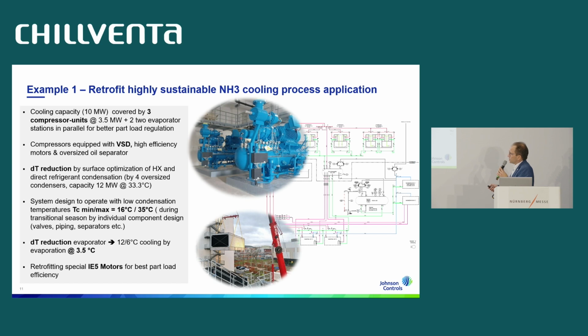We equipped the compressors with a variable speed drive and high efficiency motors and an oversized oil separator to keep temperatures very low, which is also gain in efficiency. And then we were able to reduce also the delta T, the temperature reduction, by simply optimizing our heat exchanger, so for direct refrigerant condensation, and we oversized the condensers a little bit, which is a higher capex for sure, so you're paying more money because it's oversized, but on the long run, it saves money tremendously because you're saving operating costs. So we were able to have a capacity of 12 megawatt at 33 degrees Celsius.